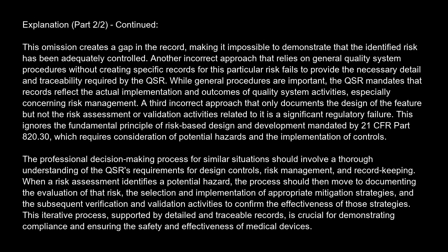especially concerning risk management. A third incorrect approach that only documents the design of the feature, but not the risk assessment or validation activities related to it, is a significant regulatory failure. This ignores the fundamental principle of risk-based design and development mandated by 21 CFR Part 820.30, which requires consideration of potential hazards and the implementation of controls.